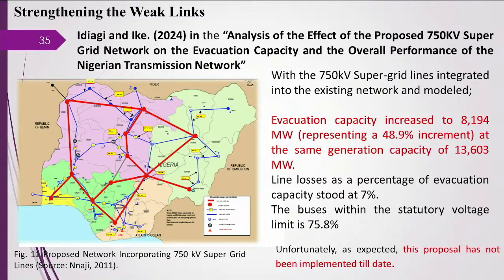We decided to review that proposal to see the impact it would have made. We modeled it by interfacing the proposed 750 kV transmission line onto the existing 330 kV and 132 kV network, and did a simulation to ascertain the evacuation capacity of this proposed network. We found that this network was able to evacuate 8,194 megawatts of the 13,603 in generation.